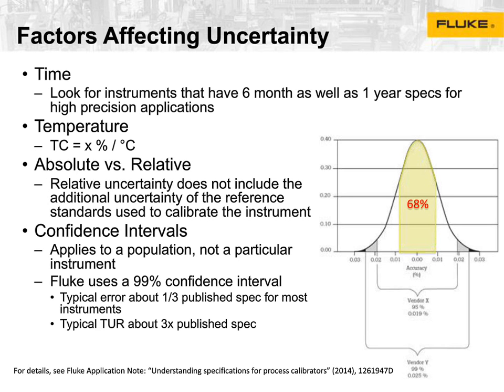The last and sort of the hardest to talk about is confidence interval. This is something that each manufacturer decides, and most manufacturers don't publish, so it can be very difficult. Usually if you ask the manufacturer, they'll tell you. And basically what this says is that after the quoted time, so 6 months or 1 year, what proportion of their population will give a reading that is out of specification? And so the key thing here is it applies to a population. So most instruments will be much tighter than this, and most instruments tend to fall on a bell curve like I've got here. And so if one manufacturer uses a 95% confidence interval, that would be vendor X, and the other uses a 99% confidence interval, they will actually quote different specifications even if the performance is identical.